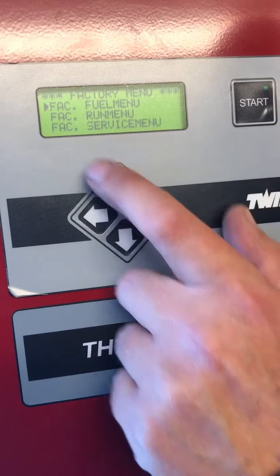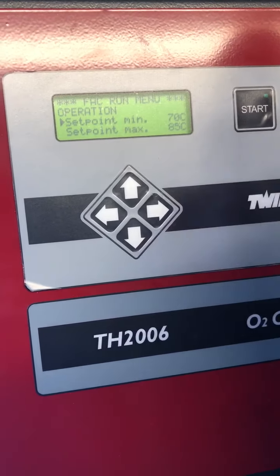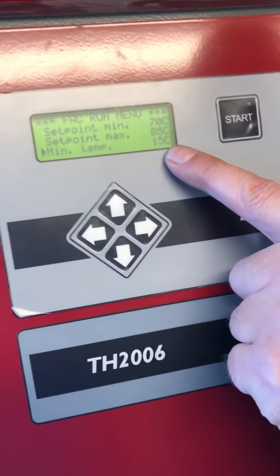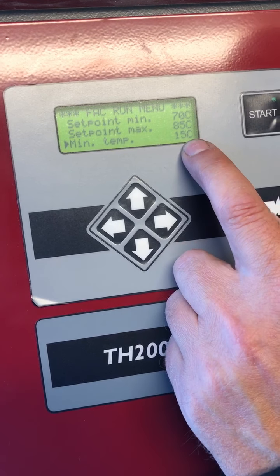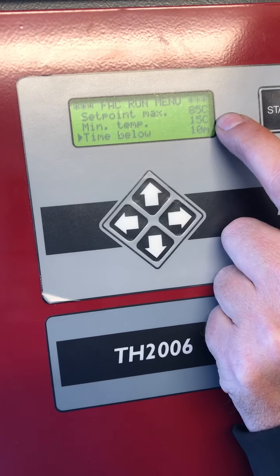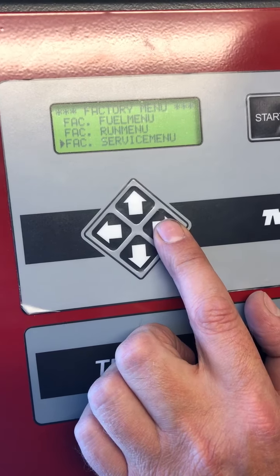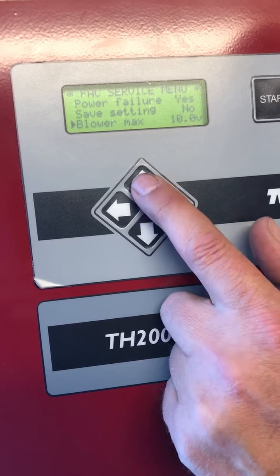Here you can change the factory fuel menu and run menu. If you go into run menu and change your temperature, here you can change what temperature range you can set. And low temperature means 15 degrees under — if you have set 70 degrees on the boiler, the mark on the front page before the temperature will disappear 15 degrees under the wanted temperature, so at 55–56 degrees that mark disappears. But if you drop 15 degrees under the set temperature for more than 10 minutes, it'll stop and write 'low temperature'. Everything you change under the password, you have to go to password 37, factory service menu, press right, go down to the bottom, and save settings.